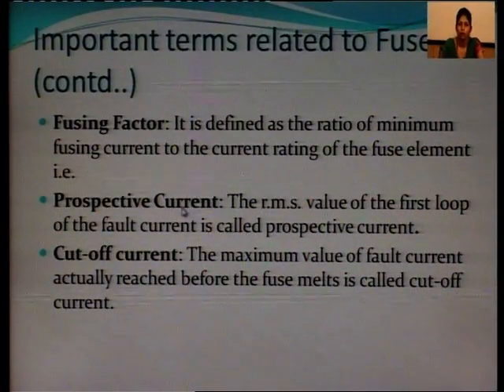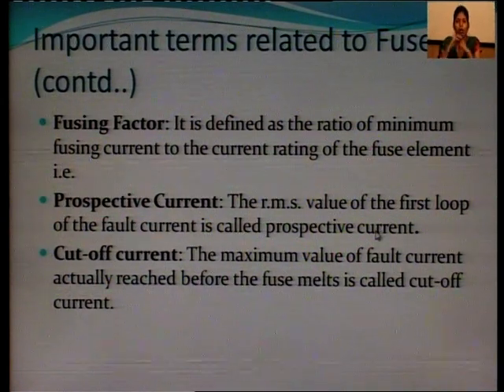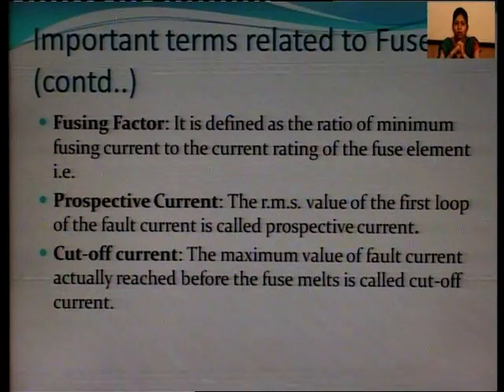Next is prospective current. The RMS value of the first loop of the fault current is known as prospective current. So after a fault occurs, the RMS value of the first loop of the fault current is called prospective current.